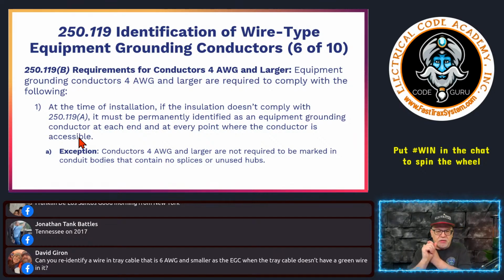So all junction boxes. If you have a panel to a box and you have a midway junction point in a box, you'd have to do it at the panel, you'd have to do it at the end box, and you have to also identify it at the junction box. And people say, well, tape is not permanent. Yes, it is. If you wrap it at the point of termination, you don't have to wrap the entire conductor. It just says at the point where the conductor is accessible and where it's terminated, okay? So you just put one wrap around it of green tape and it's fine.